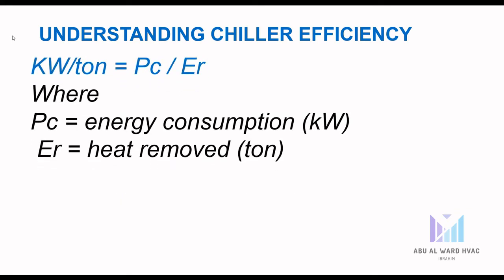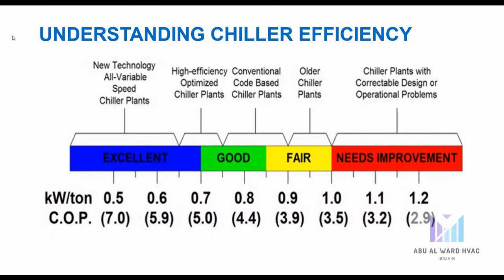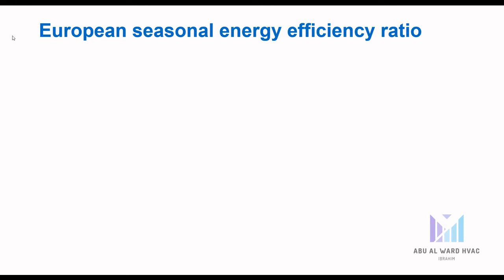Kilowatts per ton also equals power consumption (kW) divided by heat removed (ton). Looking at the rating diagram for chiller plants, for new variable-speed chiller technology the excellent range is starting from 0.5 kW/ton, while the bad amount is 1.2 kW/ton. Correspondingly, COP starts from 7 for excellent new technology, while bad plants have only 2.9 COP.